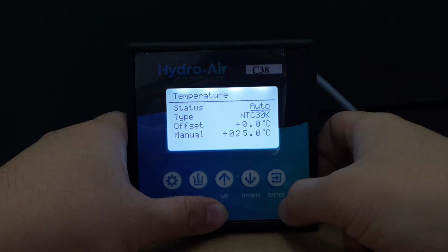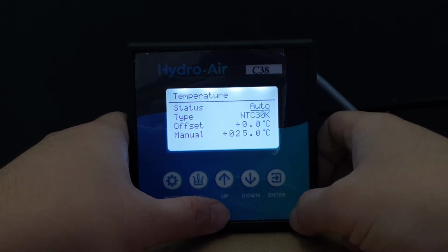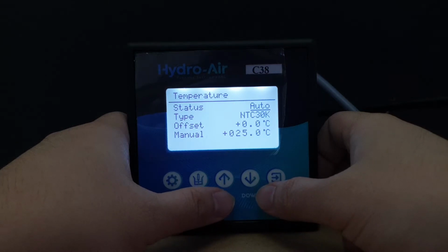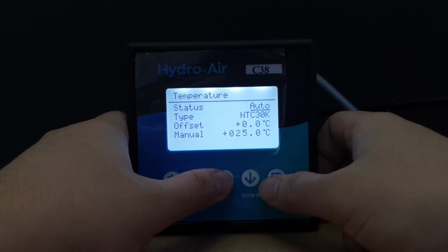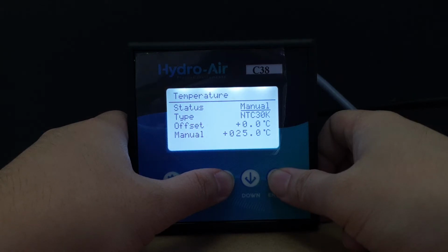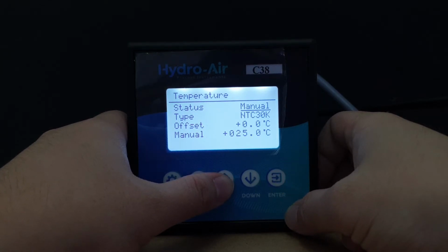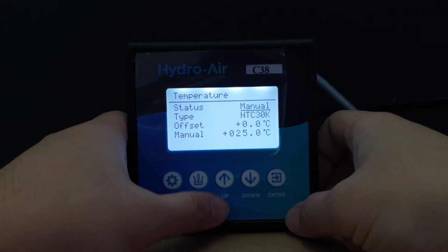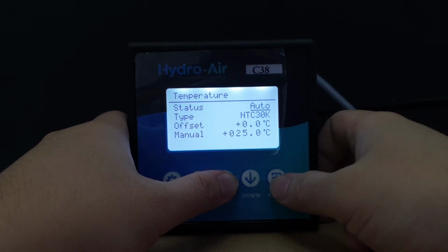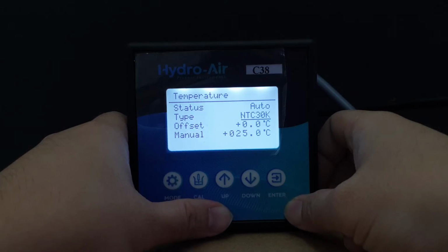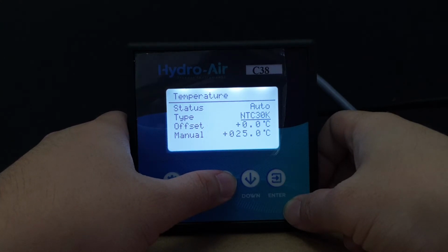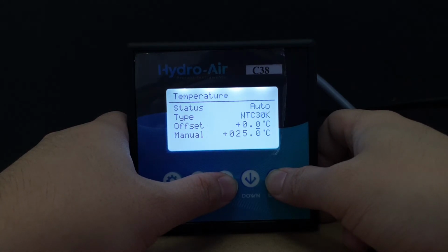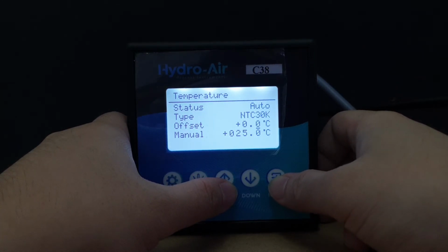At the temperature setting, you are able to select the type of temperature compensation that you prefer, either automatic or manual. Normally, a conductivity sensor comes together with a temperature probe, so you would want to set this to auto. There are probe types that you can choose from: NTC30K and PT1000. There's an offset as well for soft tweaking, and a manual temperature input.